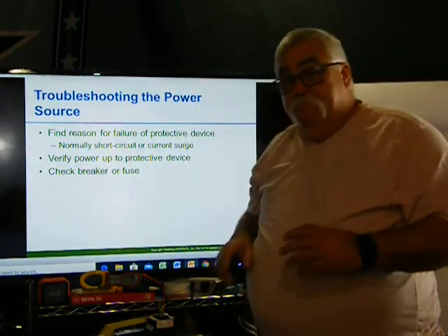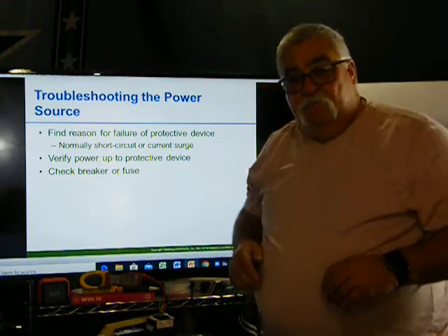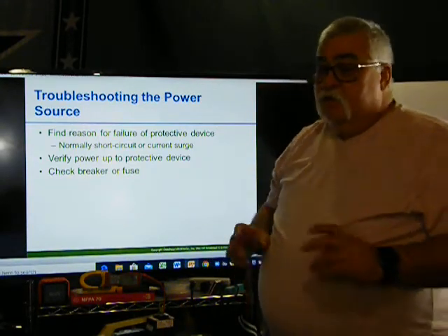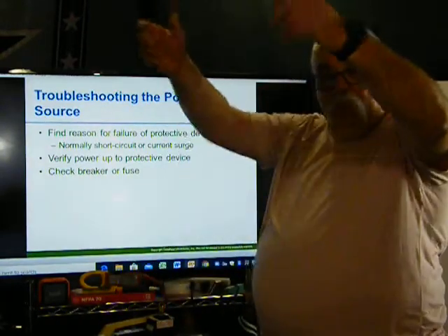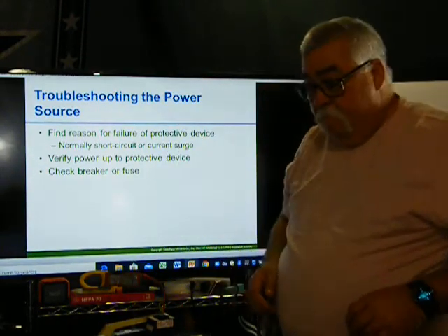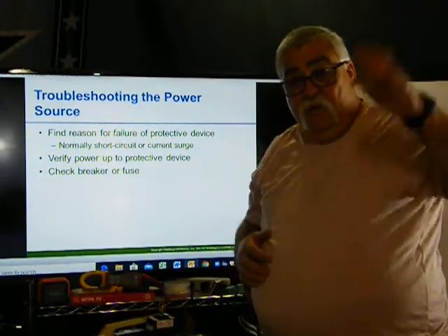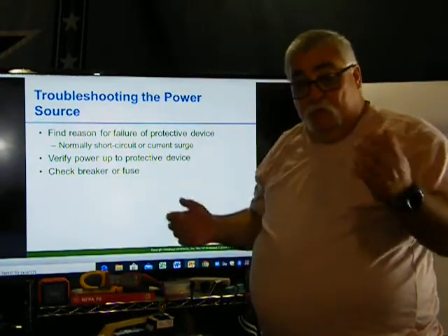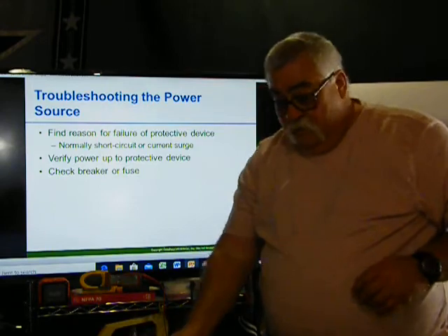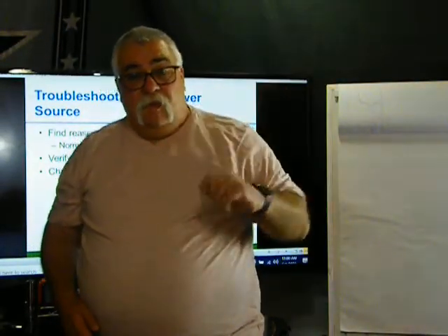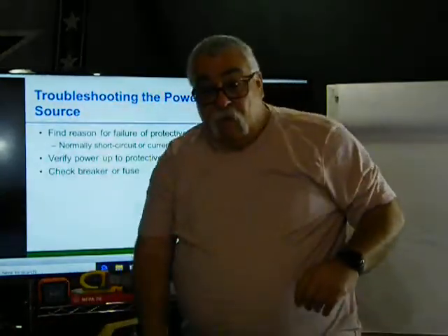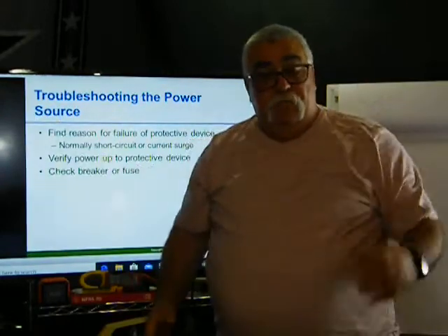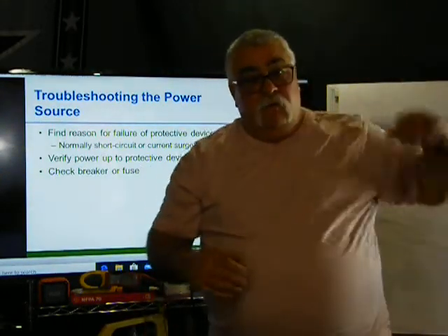Now I'm sitting there getting ready to hit the start button. And I said, you know what, Mundo, why don't you just practice what you preach? So I grabbed the cover, put the cover on, locked it in. I'm right-handed, and like I always say, use the hand you don't like. So I took a step to the right, and after I turned the breaker on, I reached up and used my left hand to hit the start button, which turned the motor on. Boom! It blew the cover off, hit me in the hand, and the cover flew to the back.